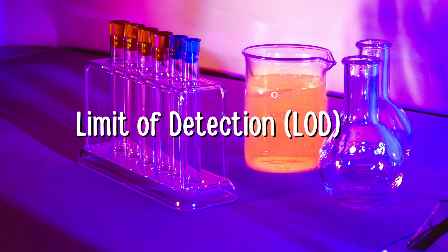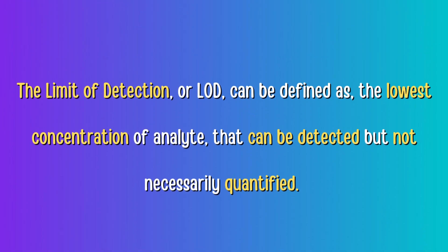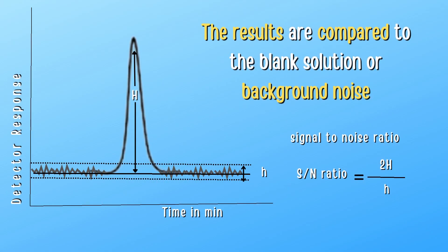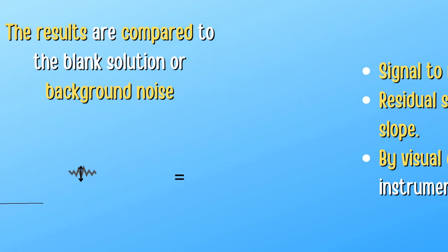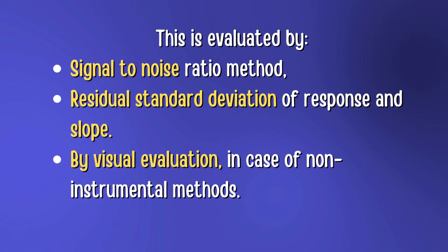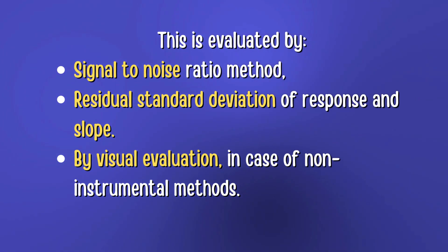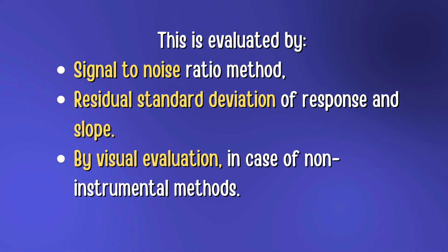Next, we will discuss the limit of detection, or LOD. The LOD can be defined as the lowest concentration of analyte that can be detected but not necessarily quantified — in other words, the lowest amount that can be reliably detected and distinguished from background noise. It is determined by performing experiments using standards with known low concentrations and comparing results to a blank solution. LOD is evaluated by signal-to-noise ratio, residual standard deviation of response and slope, or by visual evaluation for non-instrumental methods. A low LOD indicates a more sensitive method.